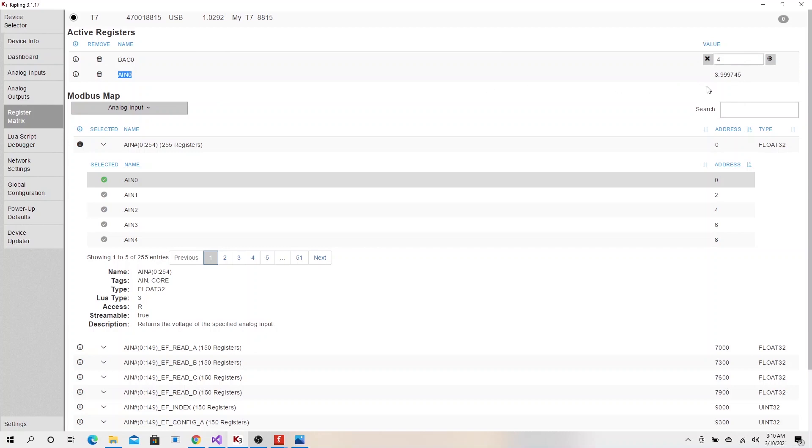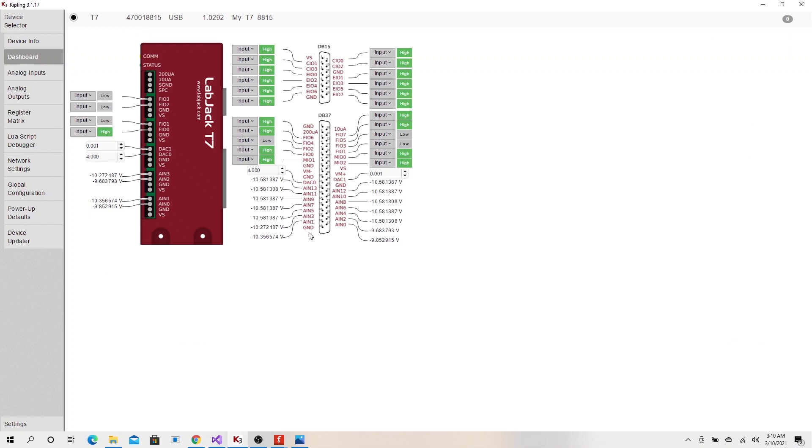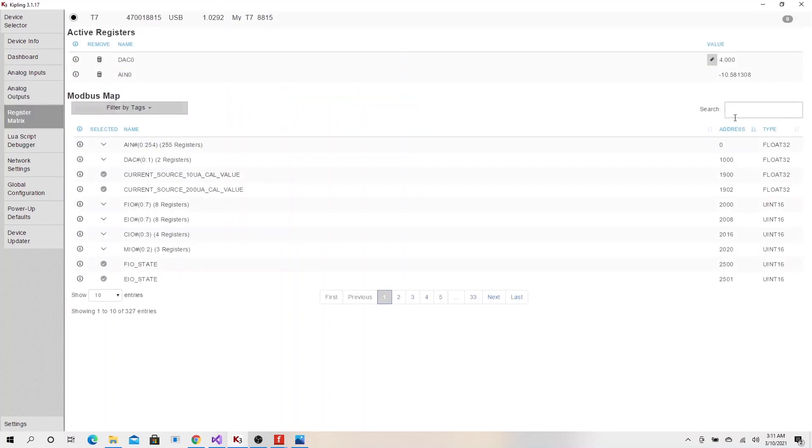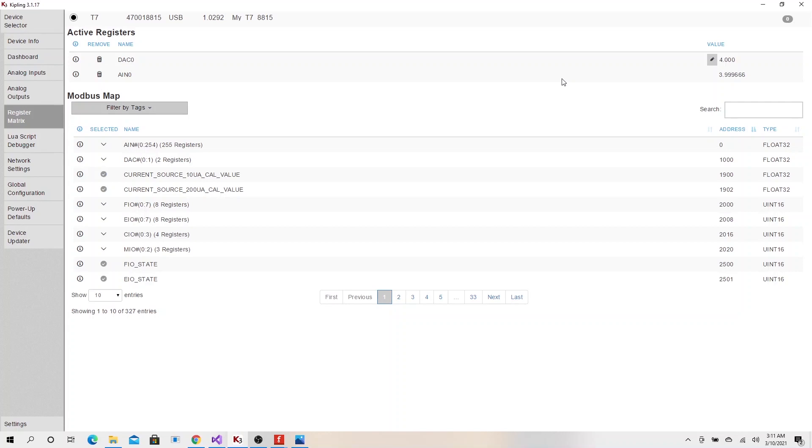Sounds good enough. Now let me go ahead... if I disconnect it, it will stop reading. So now it's back to the floating point. If you go to the dashboard, it's showing all the floating numbers which is negative 10. If I go back to the register, it's showing the floating number which is negative 10. So you have to watch and make sure that you are not reading the floating number thinking that you are reading a true value. I'm connecting it back. Now I connected it back and everything looks amazing.